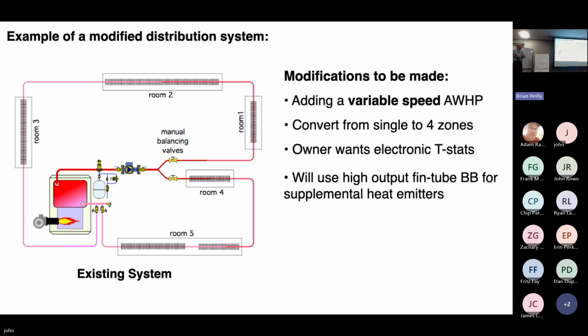Here's an example where we're taking what's called a split series distribution system. Some of the old hydronic systems, what they would do is come out of the boiler and then they have a split. One loop would go around one side of the house and the other loop would go around the other side. Then they come back together. So what we're going to do is convert that. The modifications are listed over there on the right.